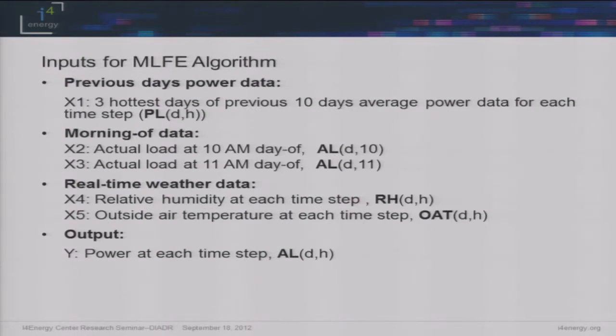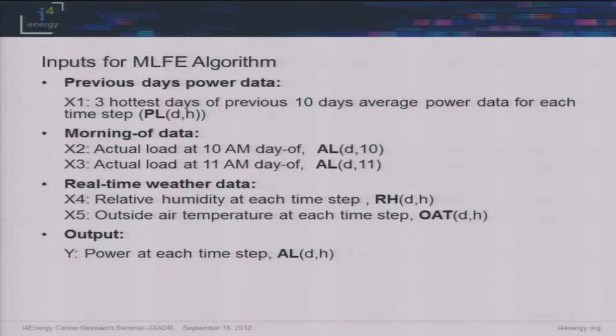Similarly to the BP3 method that LBNL used, we used the three hottest days of the previous 10 as an input. We also had two inputs from the morning of, similarly to the correction factor approach. We used some real-time weather data — relative humidity and outside air temperature at each step — and then we basically have an output of power. If we wanted to, we could actually use a weather forecast for humidity and outside air temperature looking ahead, though that adds some uncertainty, which is a trade-off.